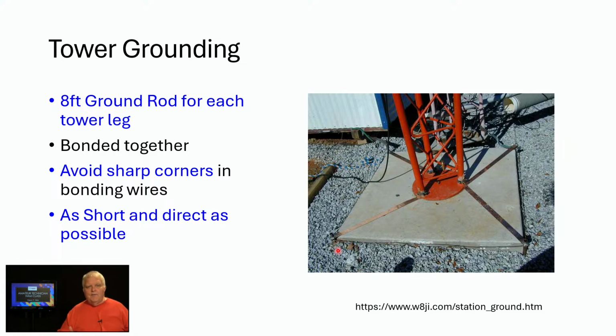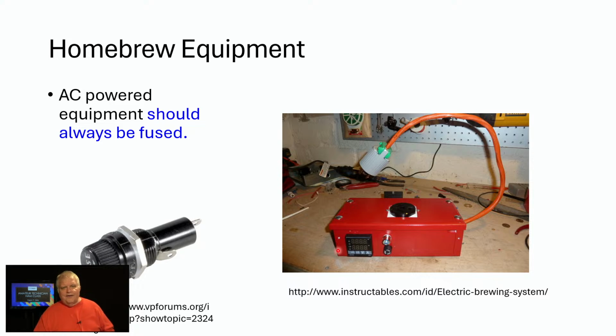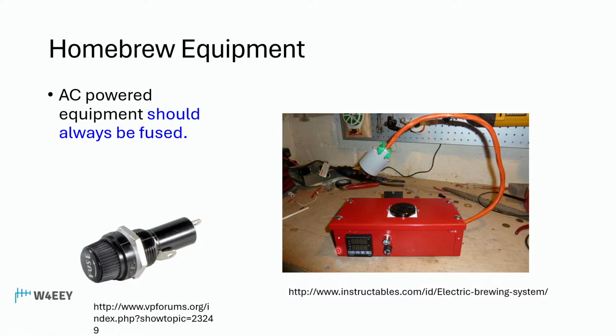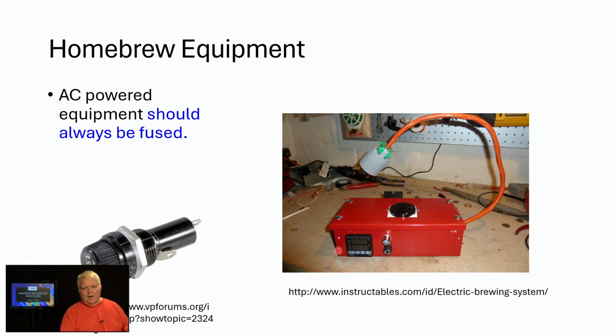It's not so common anymore, but back in the day we used to build our own equipment. The rule was that AC powered equipment should always have a fuse, and the fuse must be located in the black wire. If it's AC powered, you want the fuse where the power comes into the device, not on the return, but on the black wire — the source of power coming from the panel or outlet. And if you're building or have equipment, keep in mind they won't look like this; these are pretty old and ugly.